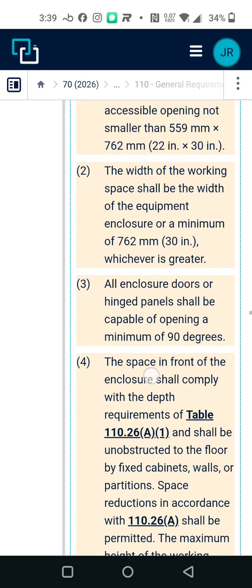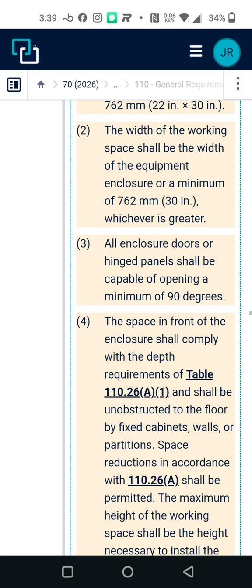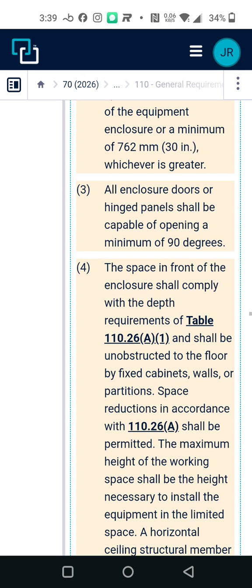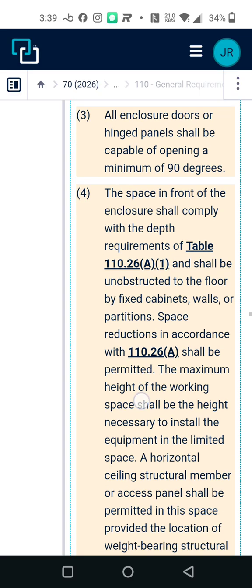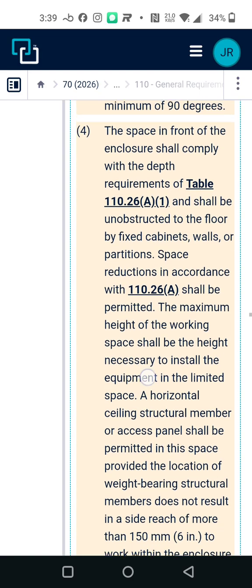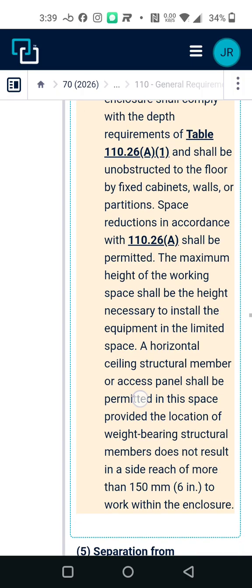The width of the working space should be the width of the equipment enclosure, a minimum of 762 millimeters, or 30 inches, whichever is greater. All enclosure doors or hinged panels should be capable of opening. The space of the enclosure should comply with the depth requirements.